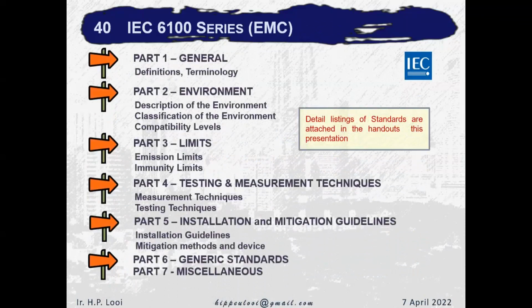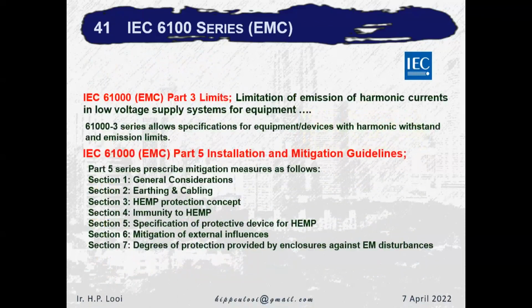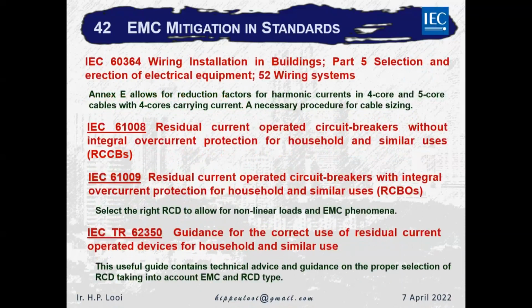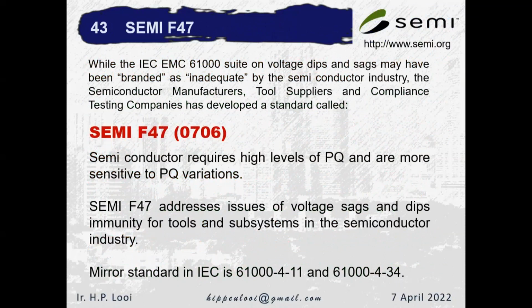Okay, this is the list of the IEC 61000 standards. I have a detailed list which is actually included in the handout. You also have mitigation and immunity standards, and for practitioners, RCD: how do you specify RCD? Because RCD is a common issue for those who are practicing, especially design engineers, SEMI F47 is a very important issue. It is also mirrored in 61000 part 4, but SEMI F47 has a higher standard.